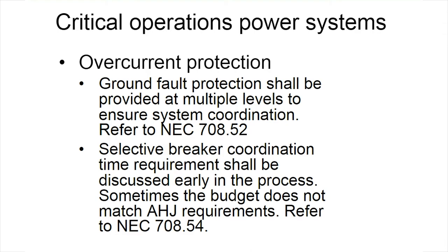So you have to agree and see what you want to do. In the case of COPs, it is required, 708.54. You have to provide selective coordination, and it's important to agree at what level. COPs doesn't follow 99. COPs just tell you that they need to be required. So agreeing to a level of coordination early in the process will definitely help you define a good budget. If they require 100% coordination, then you need to be prepared, because that will be a big impact on your budget, and you probably will end up oversizing breakers to take care of that. It's not impossible, it just requires more separation between breaker sizes at each level.